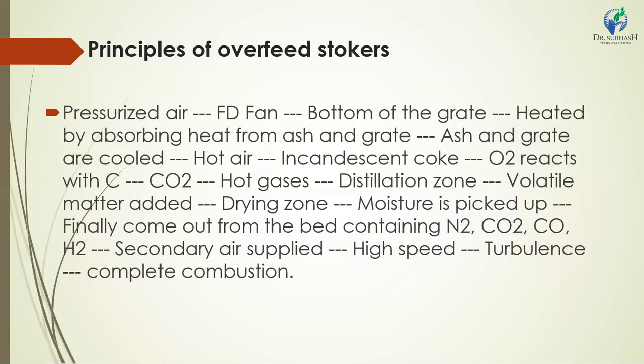The gases that enter the boiler contain nitrogen, carbon dioxide, oxygen, and water particles, and some carbon monoxide if burning is incomplete. During combustion, the ingredients of coal are continuously lost as carbon, and only ash remains, which falls through the grate into the ash pit. So this was the overfeed stoker's working principle.